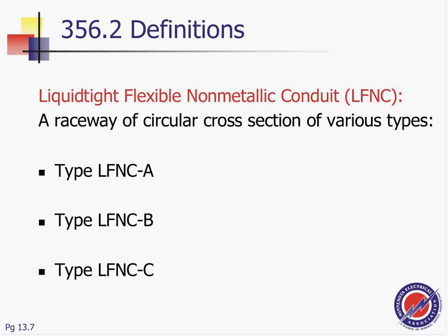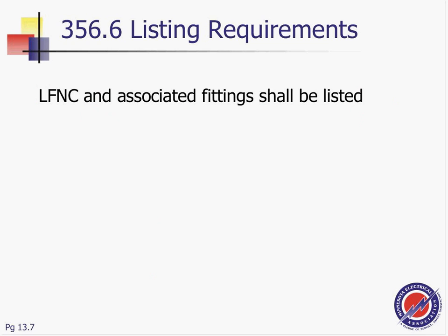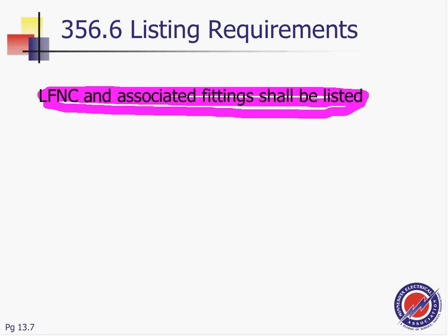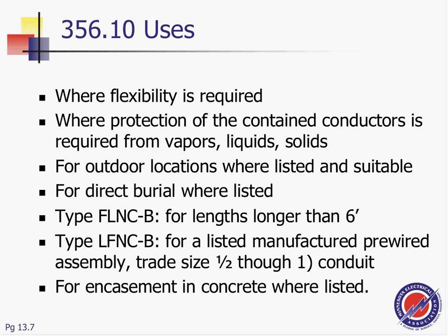Conduit or raceway comes in three types. There is type A, type B, and type C. It's very important that it comes in three types. So Liquidtight flexible nonmetallic conduits, I can't emphasize the word non enough, all of them come in three types. It comes with all its associated listed connectors, so you can't just design it yourself and couple it with connectors. Okay, let's look at the uses permitted for this conduit. Very important. Where can I use it?